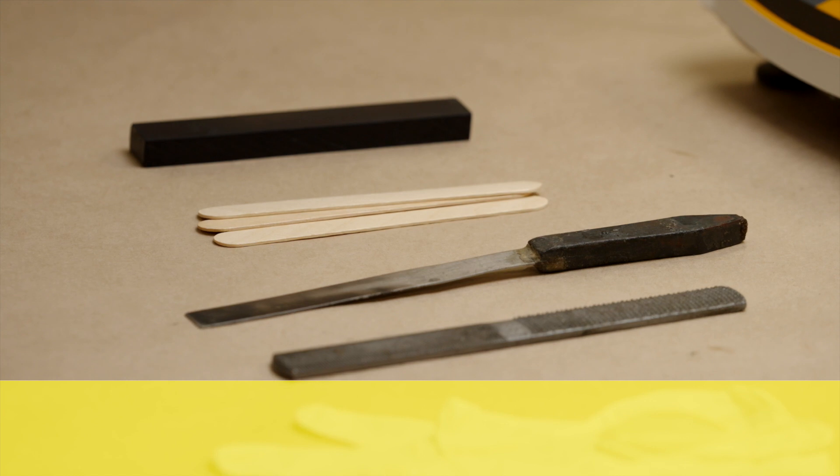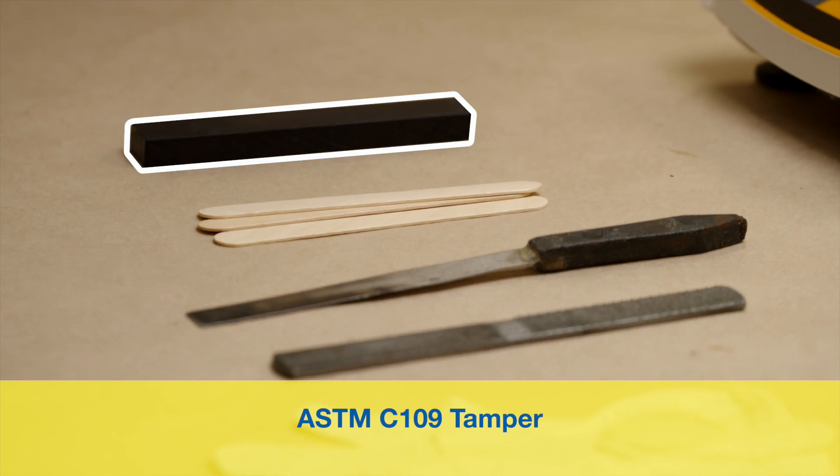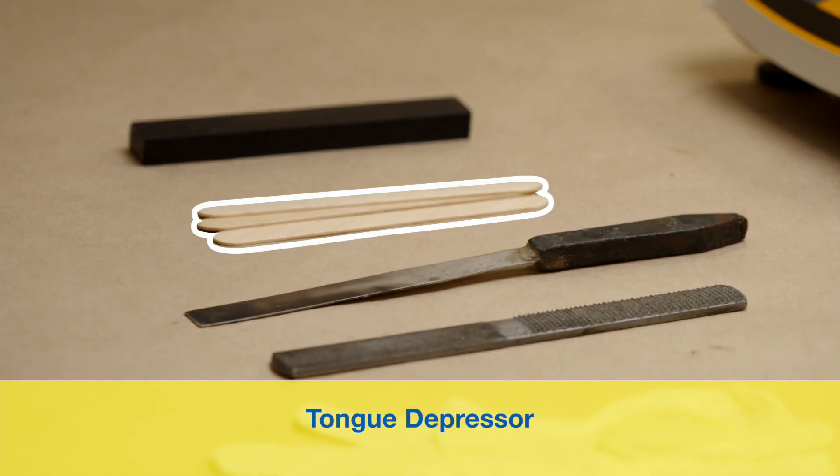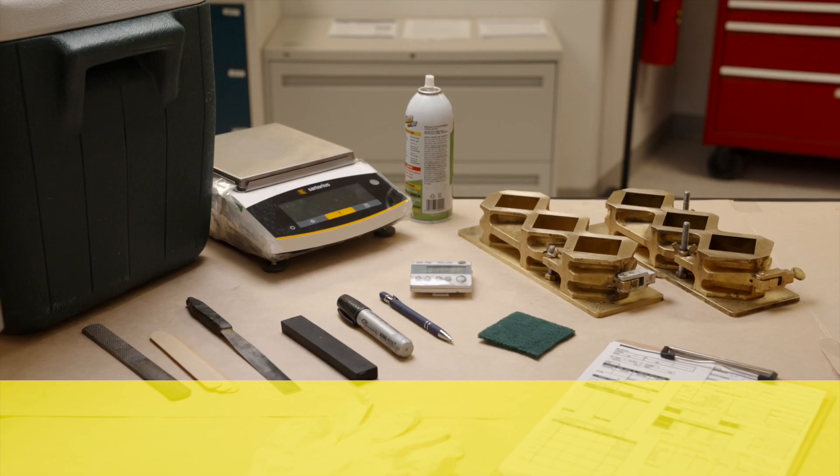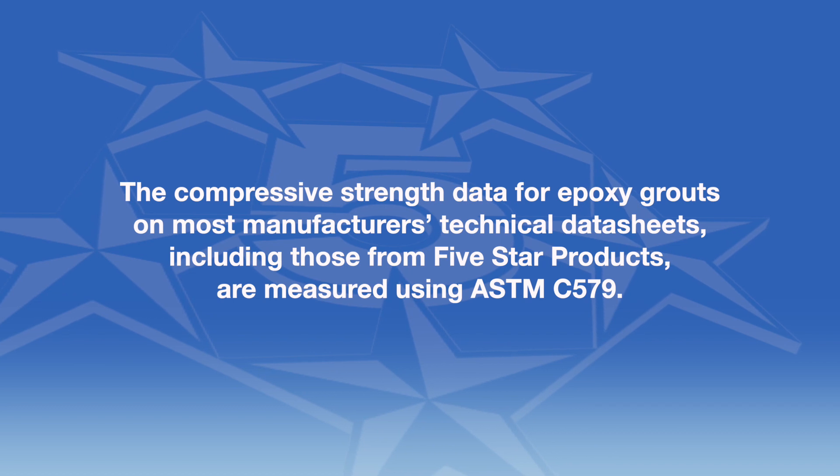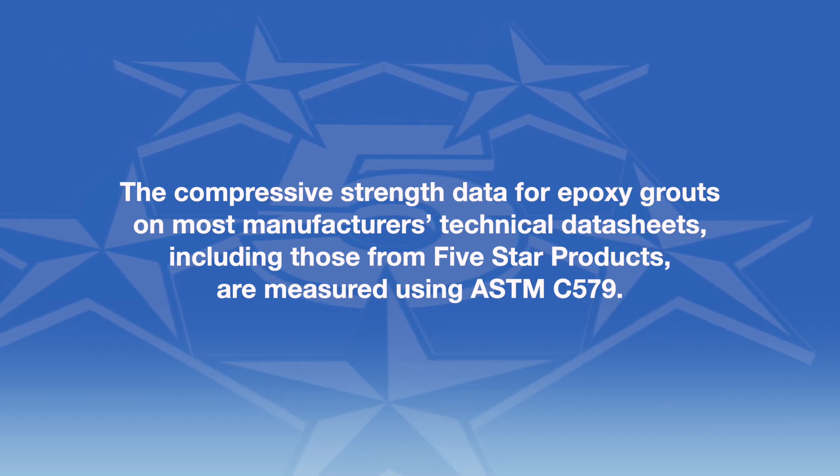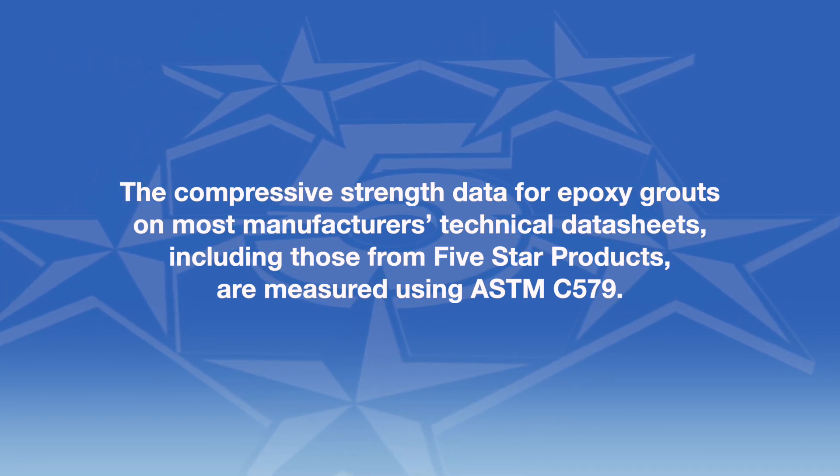Additional requirements include an ASTM C109 tamper. If unavailable, you may use a tongue depressor or spatula. You will also need a file, scale, scouring pad, permanent marker, thermometer, and record book. The compressive strength data for epoxy grouts on most manufacturers' technical data sheets, including those from Five Star Products, are measured using ASTM C579.